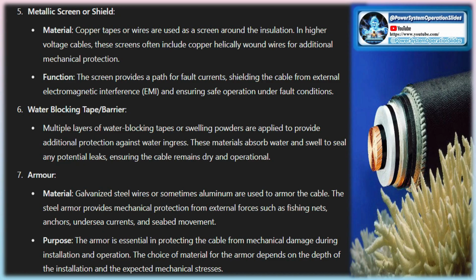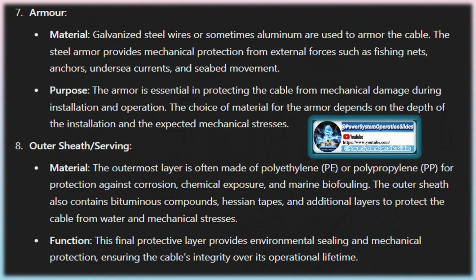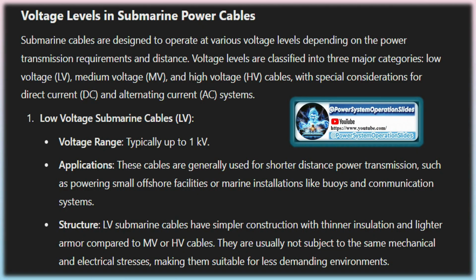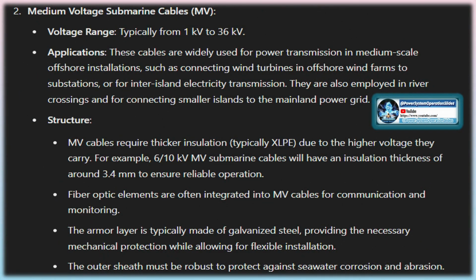Key features include water-blocked copper conductors, XLPE or EPR insulation, fiber optic elements for communication, and galvanized steel wire armor for mechanical protection. These cables are designed to operate at various voltage levels, withstand extreme conditions, and meet stringent international standards. Submarine cables for power systems are critical infrastructure that enable the transmission of electricity across bodies of water, connecting power grids between continents, islands, or offshore energy platforms like wind farms or oil rigs. These cables are categorized based on their voltage levels and construction, and they are engineered to handle the specific challenges posed by the underwater environment.